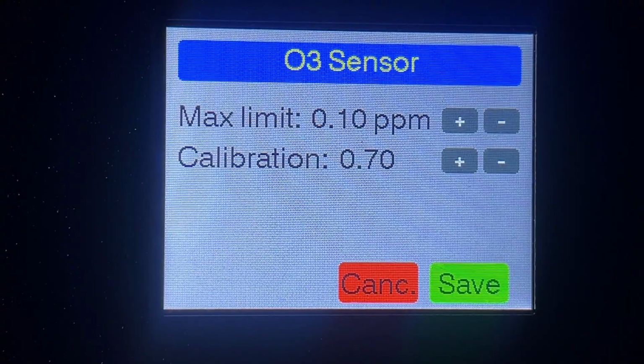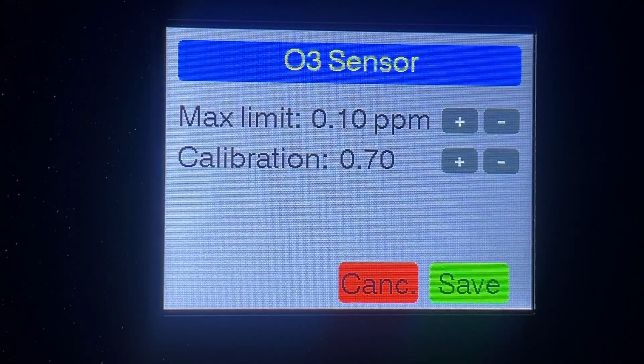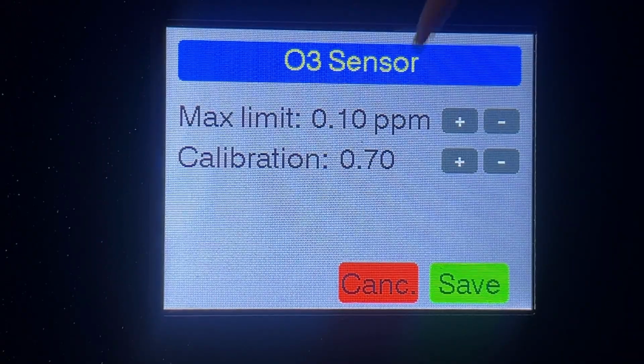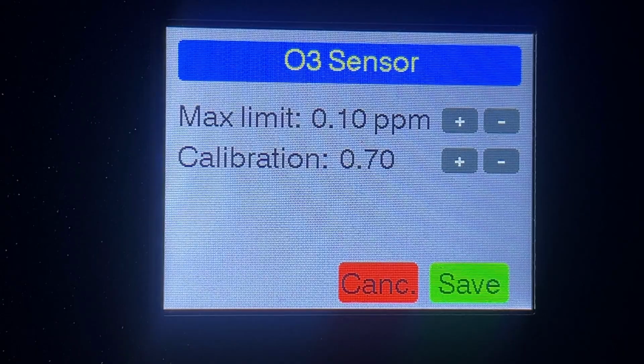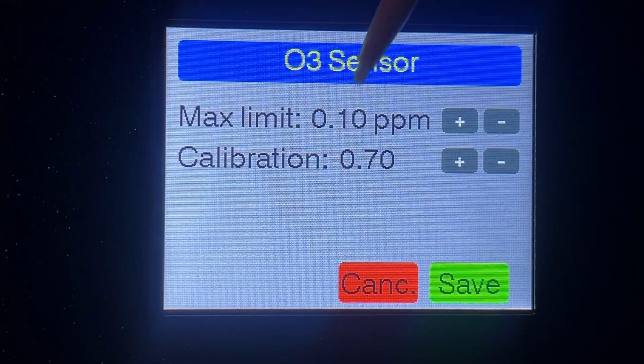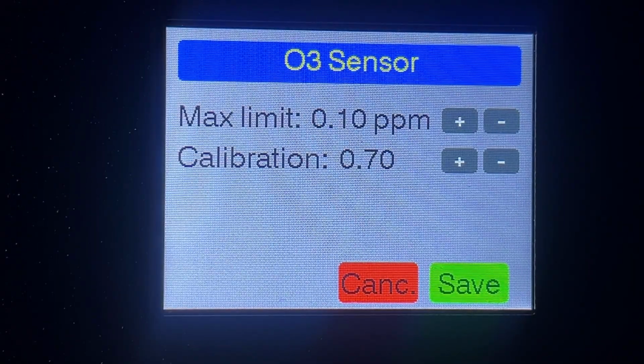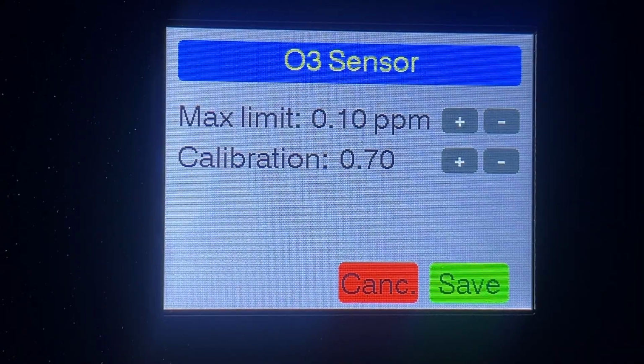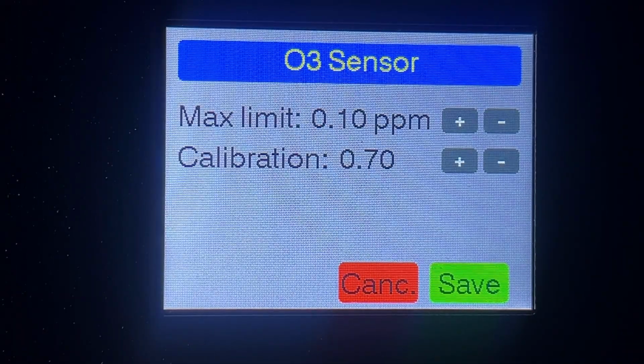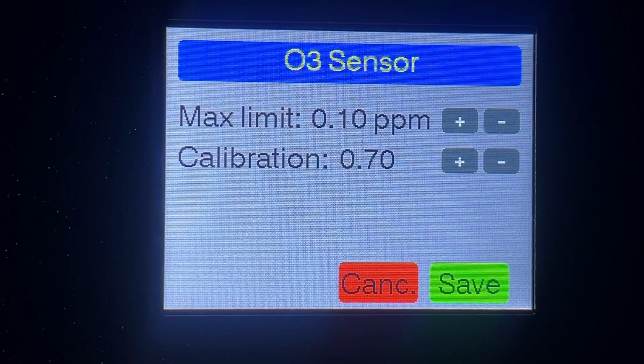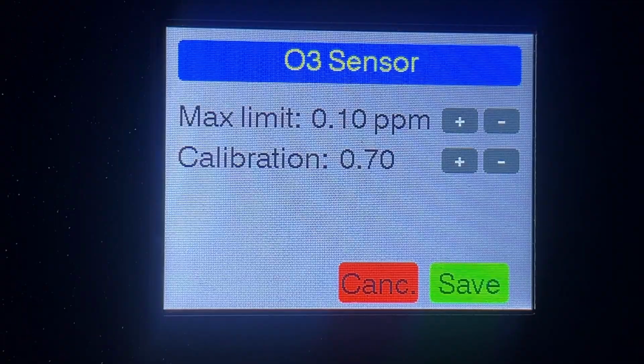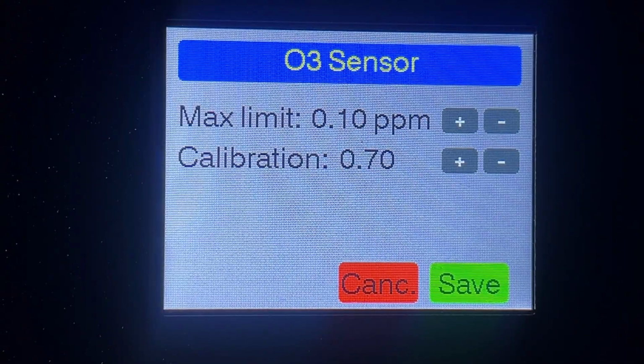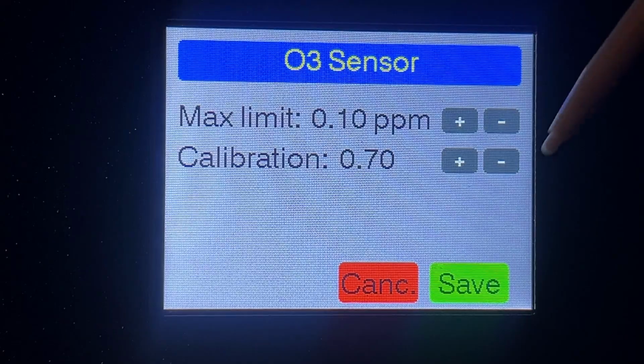Our ozone here is for the sniffer. We have the sniffer sensor. We just tell them the limits of parts per million of ozone we want, and the calibration of the sensor. When we reach 0.1 parts per million of ozone in the air, it will send us a signal. This display will turn red, and it will tell us that there is a high concentration of ozone in the area. It's made for people who are a little bit sensitive to ozone. When there is a lot of ozone in the area, you can have a little headache and you can feel a little dizzy. So we don't want that.